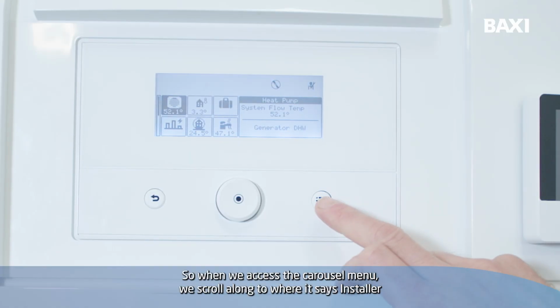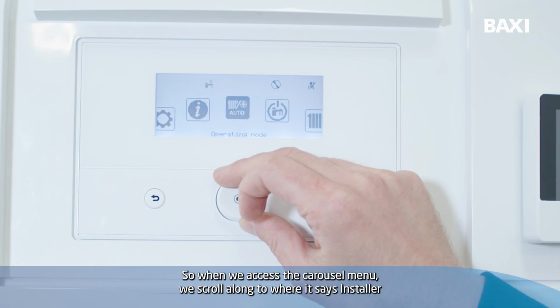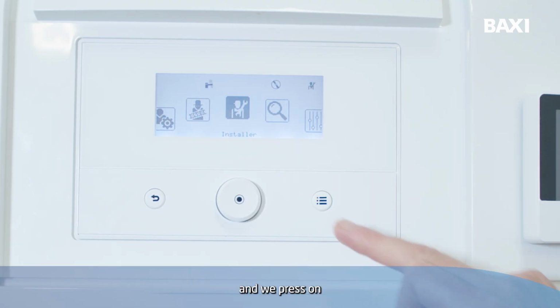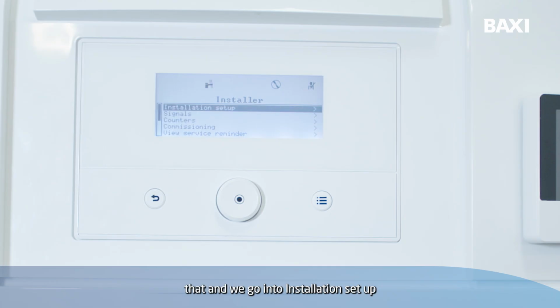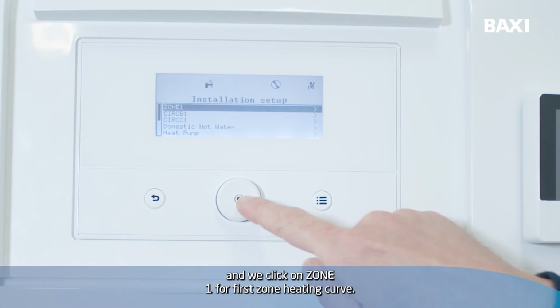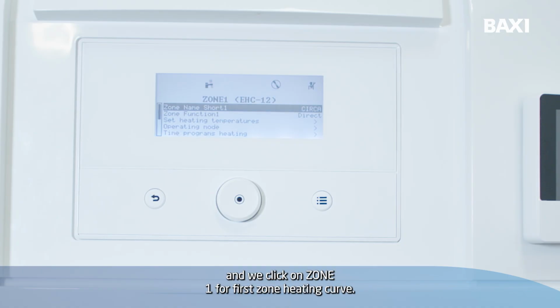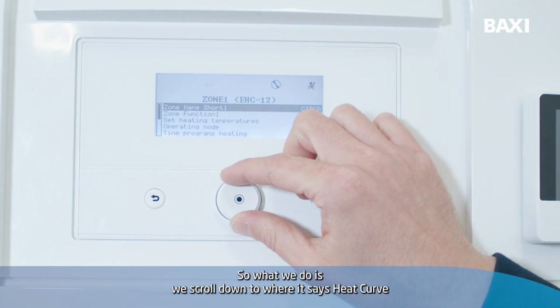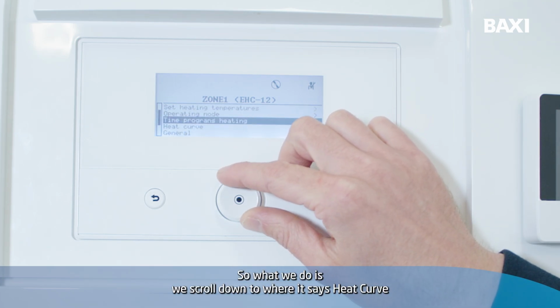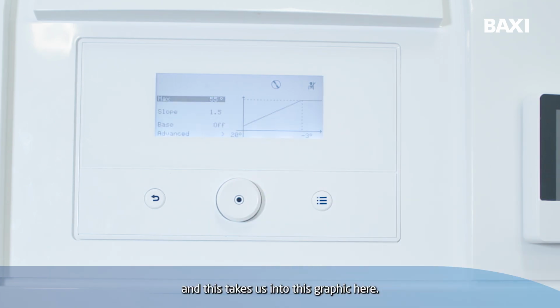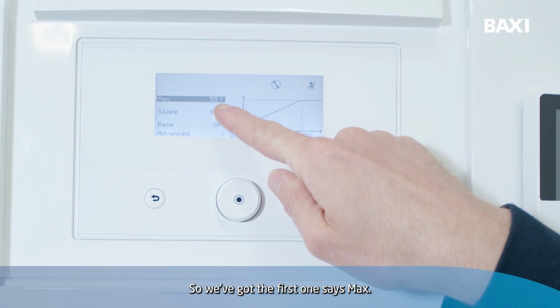So when we access the carousel menu, we scroll along where it says installer, and we press on that, and we go into installation setup, and we click on zone 1 for our first zone heating curve. If we had another zone, we can set a different heating curve for that zone. So we scroll down to where it says heat curve, and this takes us into this graphic here. So we've got, the first one says max.